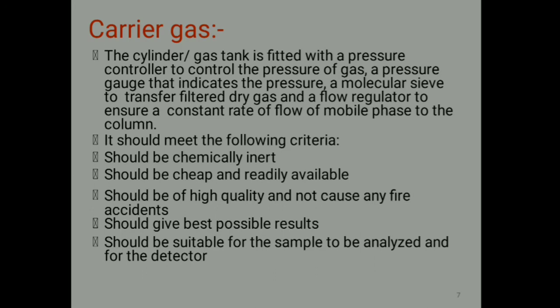Let us discuss the different parts. First, we have the carrier gas. The cylinder or gas tank is fitted with a pressure controller to control the pressure of the gas, a pressure gauge that indicates the pressure, a molecular sieve to transfer filtered dry gas, and a flow regulator to ensure a constant rate of flow of mobile phase to the column. It should meet the following criteria: should be chemically inert, should be cheap and readily available, should be of high purity and not cause any fire accidents, should give best possible results, and should be suitable for the samples to be analyzed and for the detector.